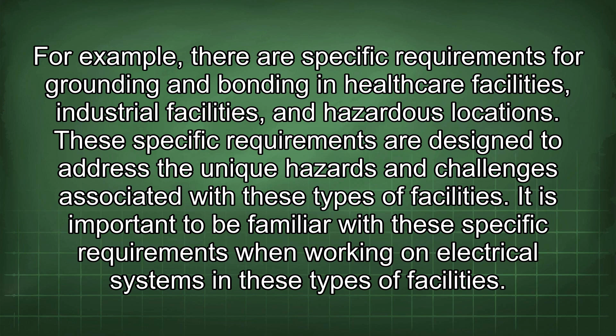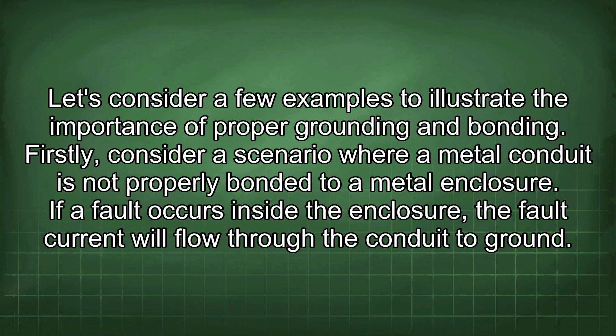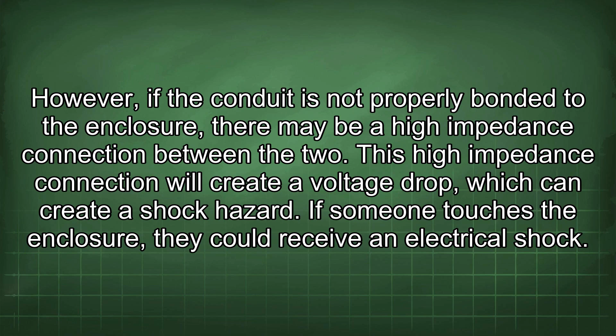Let's consider a few examples to illustrate the importance of proper grounding and bonding. Firstly, consider a scenario where a metal conduit is not properly bonded to a metal enclosure. If a fault occurs inside the enclosure, the fault current will flow through the conduit to ground. However, if the conduit is not properly bonded to the enclosure, there may be a high impedance connection between the two. This high impedance connection will create a voltage drop, which can create a shock hazard. If someone touches the enclosure, they could receive an electrical shock.